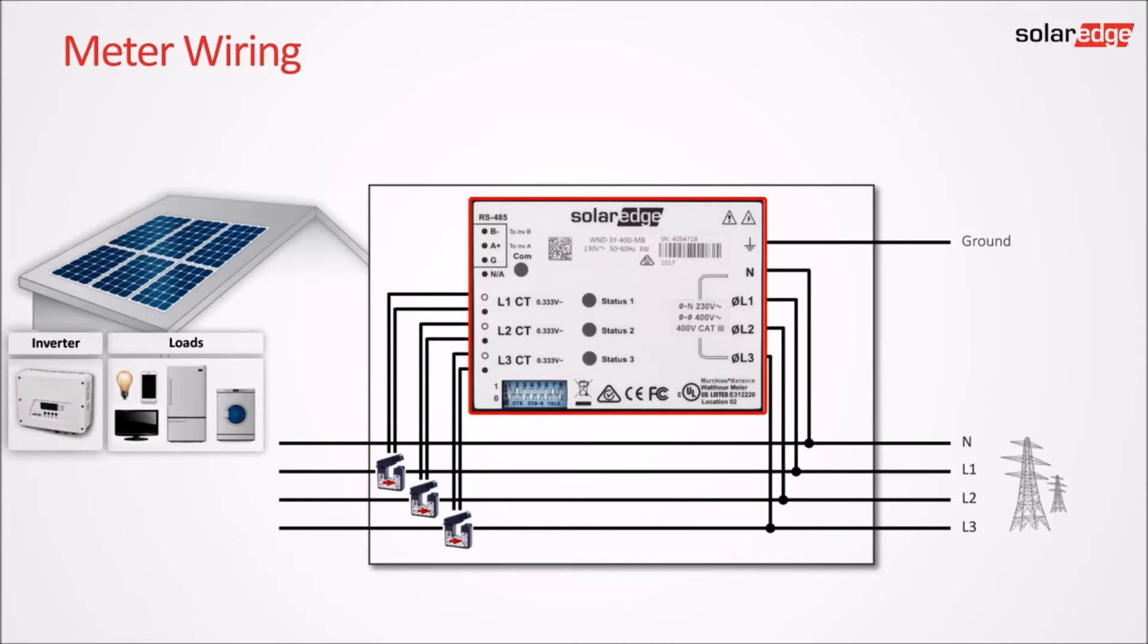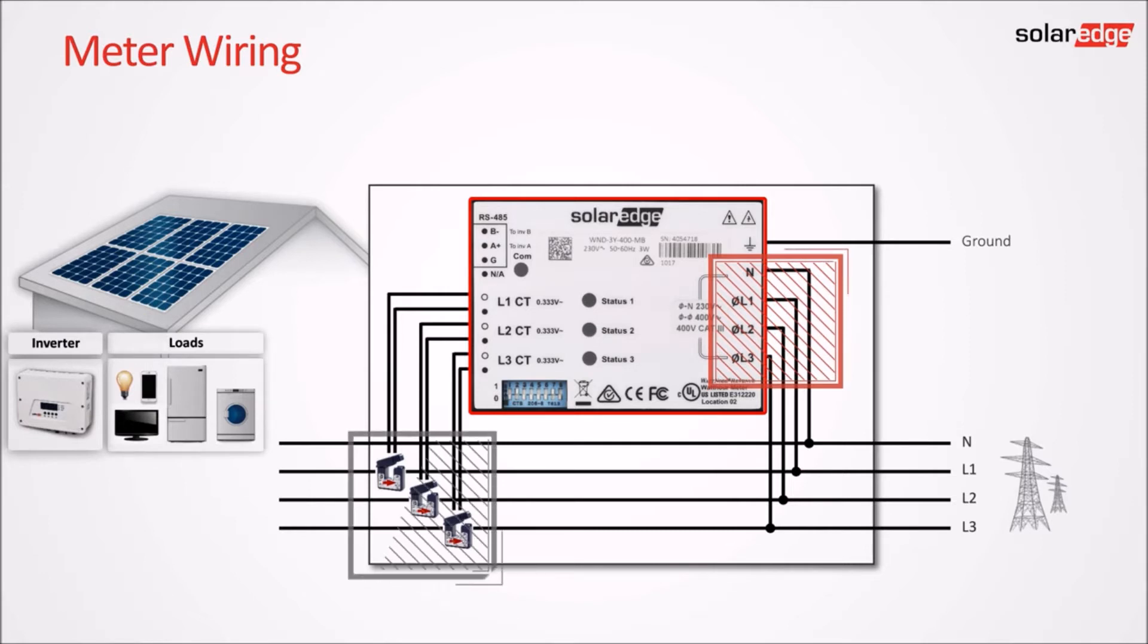When wiring the meter there are three types of connections that need to be made. Direct AC connections required to supply power to the meter. Current transformers or CTs which clamp around each phase wire and measure the current. If your utility connection is single phase only one CT is needed. RS485 for communicating the measured data to the inverter.